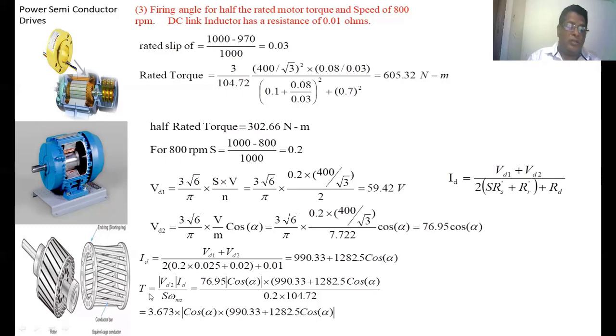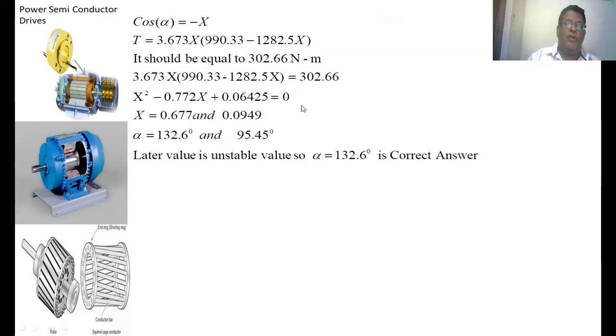The torque developed in the induction motor = Vd2·Id/(S·ωs). We know the value of Id and Vd2. Substituting all values and simplifying, we get T = 3.673X(990.33 - 1282.5X), which should equal 302.66 N-m. Solving this equation where cos(α) = -X, we get X² - 0.772X + 0.06425 = 0. Solving for X: α = 132.6° and 95.45°. The later value is unstable, so α = 132.6° is the correct answer for 800 RPM at half-rated torque.